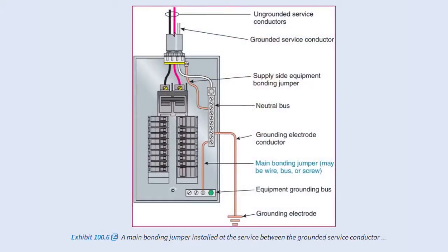We talked about a grounded conductor and a grounding electrode. A grounding electrode conductor — what are we talking about? As we can see in exhibit 100.6, it's the conductor that's used to connect the system grounded conductor or the equipment to a grounding electrode or a ground rod. It's always to a point; it's used to connect to a point on the grounding electrode system.